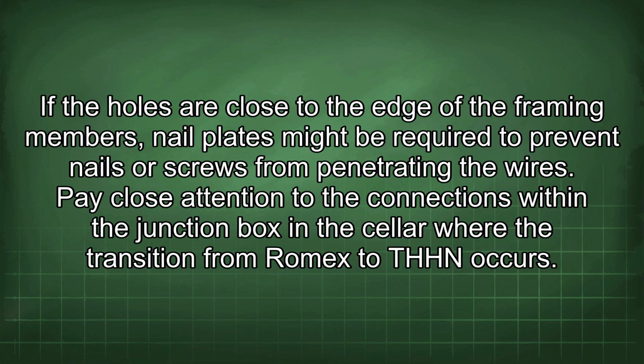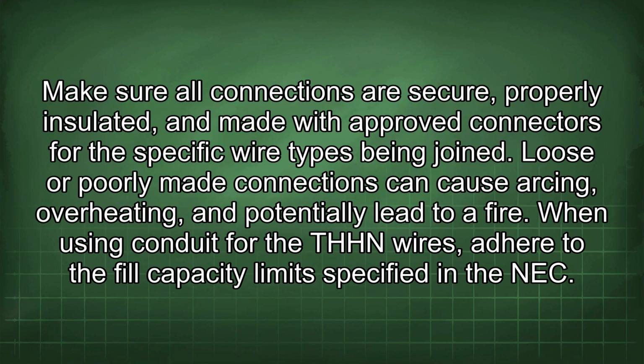Pay close attention to the connections within the junction box in the cellar where the transition from Romex to THHN occurs. Make sure all connections are secure, properly insulated, and made with approved connectors for the specific wire types being joined. Loose or poorly made connections can cause arcing, overheating, and potentially lead to a fire.